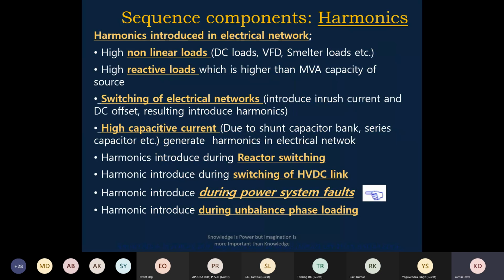Okay, how are the harmonics introduced? So non-linear loads, just DC loads, then variable frequency drives in a power plant, even in a chemical industry. Smelter loads, normally a copper plant, aluminum plant, big smelters. Smelters means nothing but rectifier transformers, and then DC loads on the downstream sides. So that is called smelter loads. Then high reactive load, for example, starting of the induction motor. An induction motor starts at low power factor, 0.2 power factor, 0.3 power factor, 0.1 power factor. So it draws more reactive power, but parallelly it distorts the waveform also.